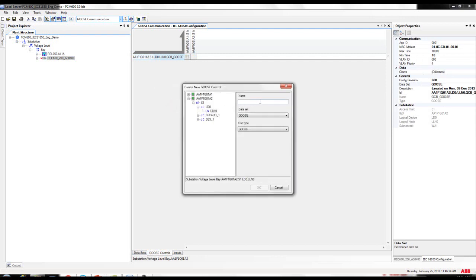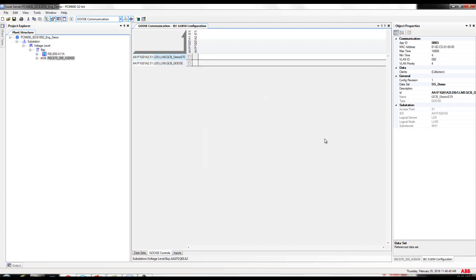Now we need to create the GOOSE control block. Click on GOOSE controls, right-click, and select the dataset — DSDemo in this particular case — and click OK. Once again, if you want to change the properties, go to the object properties section on the right side. As a practice, I match the APP ID with the MAC address number. Change the max time to one second, shorten the ID, and save the changes.